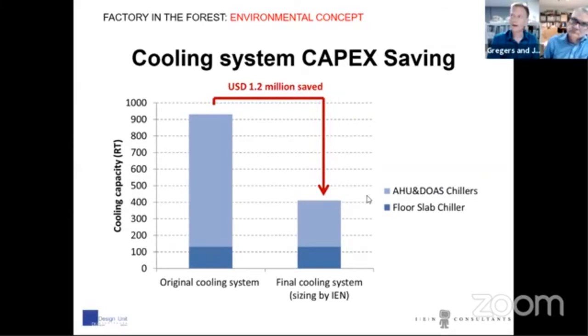One interesting thing about this factory was that we designed it so efficiently, and all the systems in the building were also very efficient. That allowed us to downsize the cooling system substantially. Instead of almost 900-plus refrigerant tons, our simulation showed we could downsize to less than half, saving 1.2 million US dollars straight off the bat in capital expenditure.